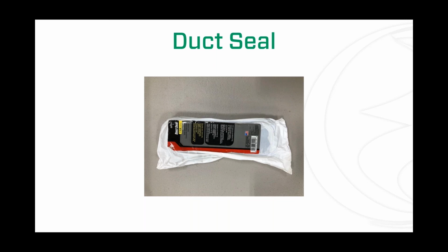If you've ever been out to a job site, at some point you're going to need to replace a pump. You're going to need to replace a float switch. And depending on how they've done it, it might be very difficult. But if they use duct seal, you can simply remove that duct seal. You can then pull in your new wire through your conduit or whatever you might have there. And then you can put your duct seal back and replace that seal. I'll tell you, you don't ever want to use silicone. Silicone in a control panel can do some off-gassing and cause some problems of its own. And spray foam is another big one that I've seen so many times I can't count.